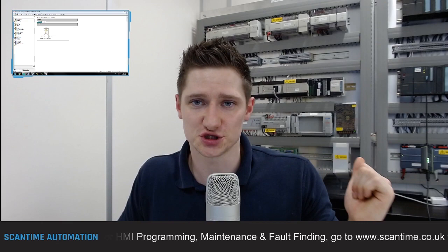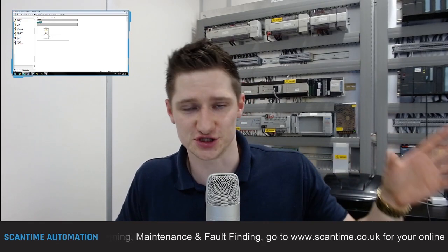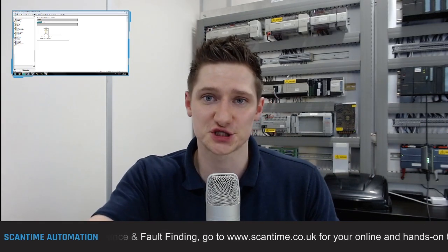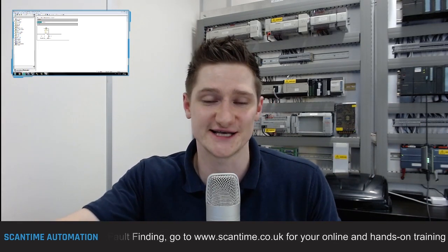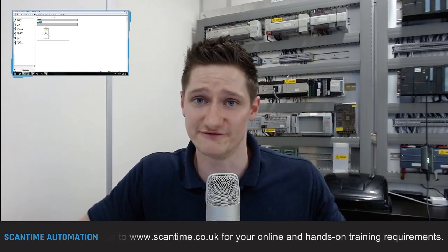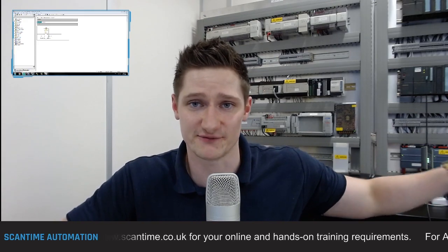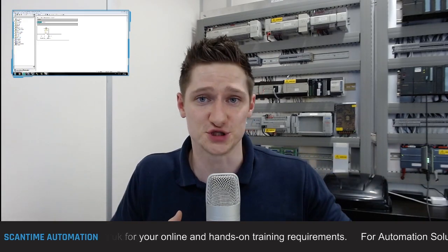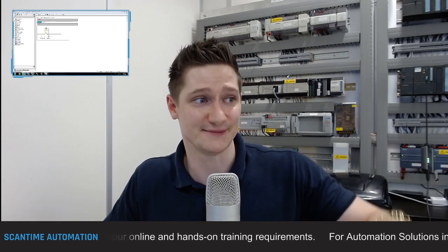Now, one thing you've got to watch out for is the current version of your PLC. If you're working with the earlier versions of the S7300 PLCs, you may not have the full selection of SFBs and SFCs that are available inside a Siemens, and that's because you work with an earlier version. It's already preloaded with its information. If you're working with newer PLCs, chances are they've got the majority of the blocks that are being created by Siemens already preloaded on its PLC.